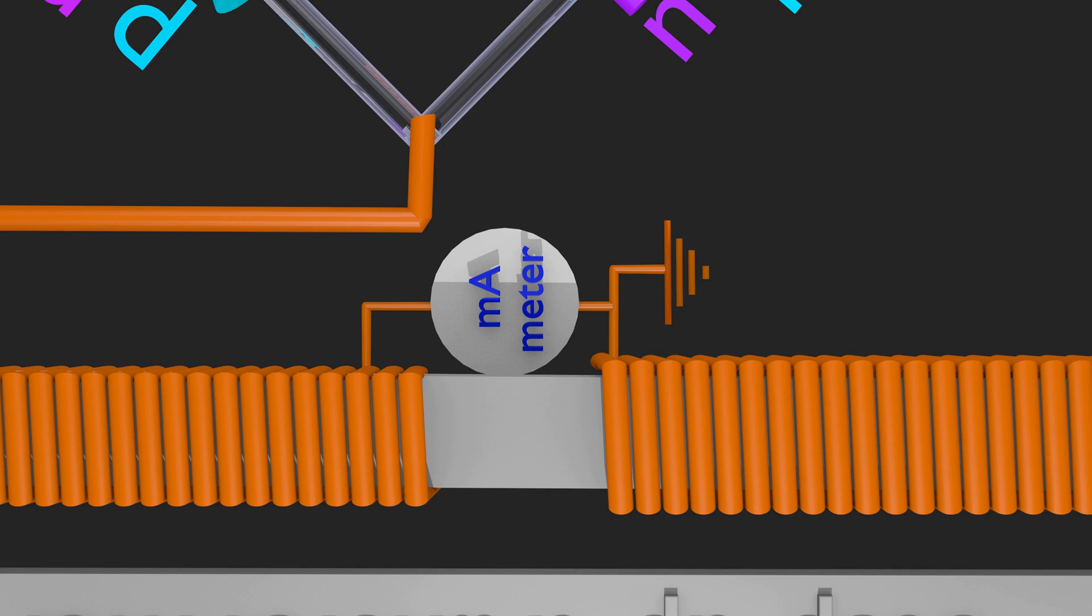A milliammeter or mA meter is placed at secondary of high-tension transformer. It indicates tube current. DC current required for moving coil MA meter is provided by rectifiers.